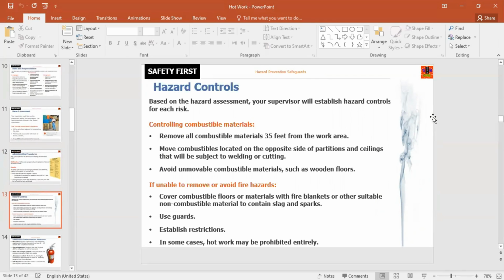Based on the hazard assessment, your supervisor will establish hazard controls for each risk, controlling combustible material. Remove all combustible materials 35 feet from the work area. Move combustibles located on the opposite side of partitions and ceilings that will be subject to welding or cutting. Avoid unmovable combustible material such as wooden floors. If unable to remove or avoid fire hazards, cover combustible floors or materials with fire blankets or other suitable non-combustible materials to contain slag and spark.